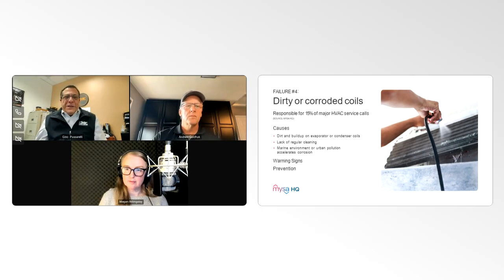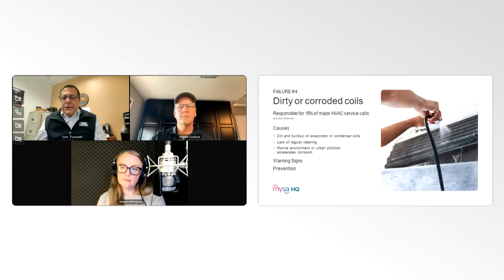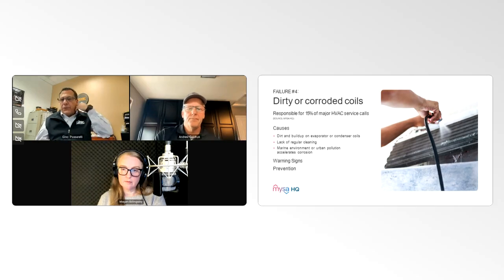It's a long conversation, but in brief, a lot of times rooftops are typically on roofs, and FMs might not have the ability to get to the roofs. What we find most common is that coils do need to be cleaned on an annual basis. And in some cases, depending on what state it is, you might have to deal with cottonwood and just natural debris that flies through the air and will clog these coils up.